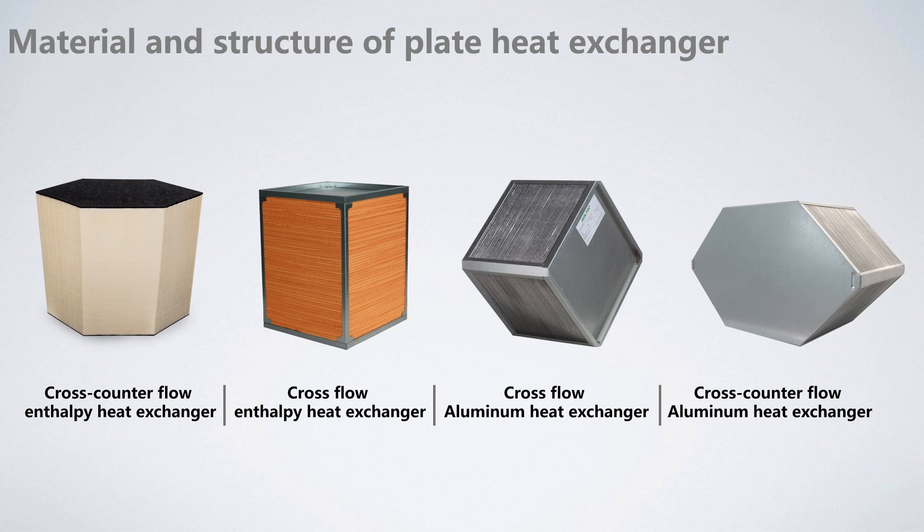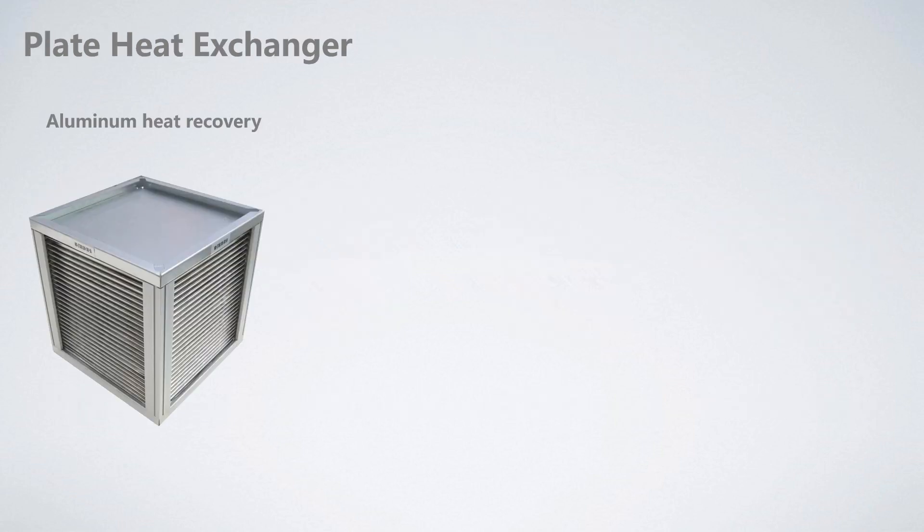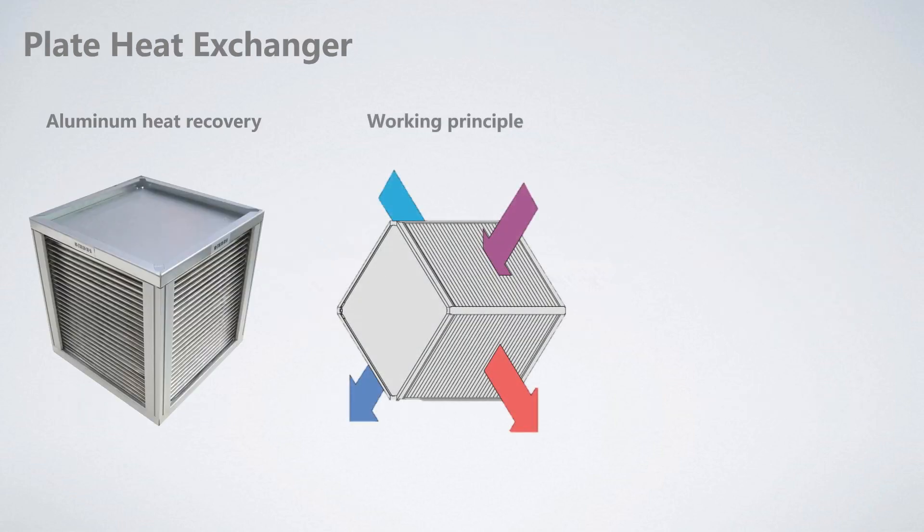Their working principles are similar. For example, like the cross flow aluminum heat exchanger, two neighbor aluminum foils form a channel for fresh air or exhaust air stream. Heat is transferred when the air streams flow crossly through the channels. Fresh air and exhaust air is totally separated.